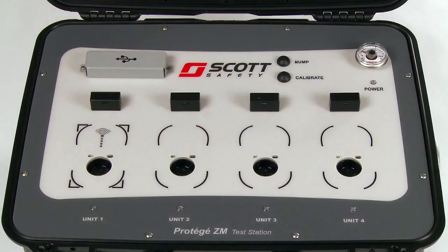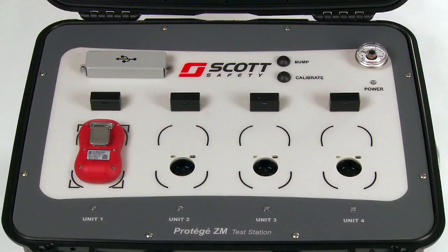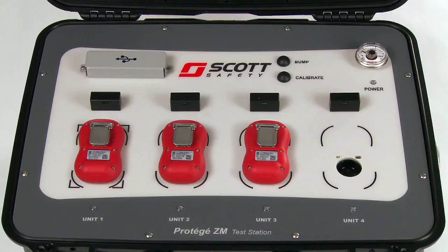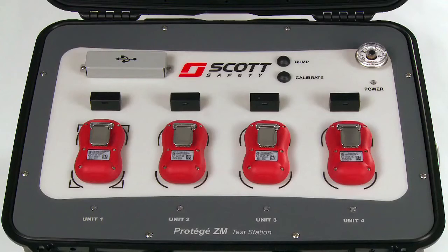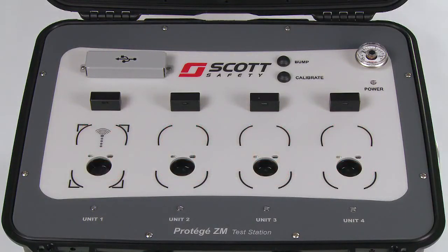The Protege ZM monitor can also be bumped and calibrated using the Protege ZM test station. The Protege ZM test station can bump, calibrate, program, or hibernate 4 monitors simultaneously. This makes maintaining a large inventory of monitors much easier. The Protege ZM test station operates on an AC outlet or via the internal rechargeable battery.